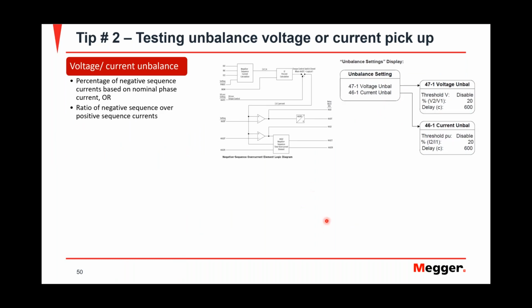Another tool that I would like to bring up, and a lot of testers are not aware of, is the fault calculator, as they call it, in the software. This fault calculator has different tools that allow you to test things a lot easier. Right? It has symmetrical components, it has impedance values. In this case, let's say you're testing a non-balanced voltage or current pickup. And there are different ways of doing it.